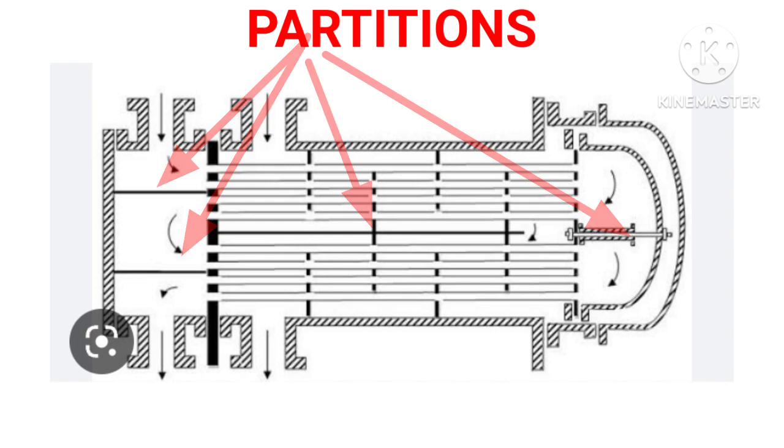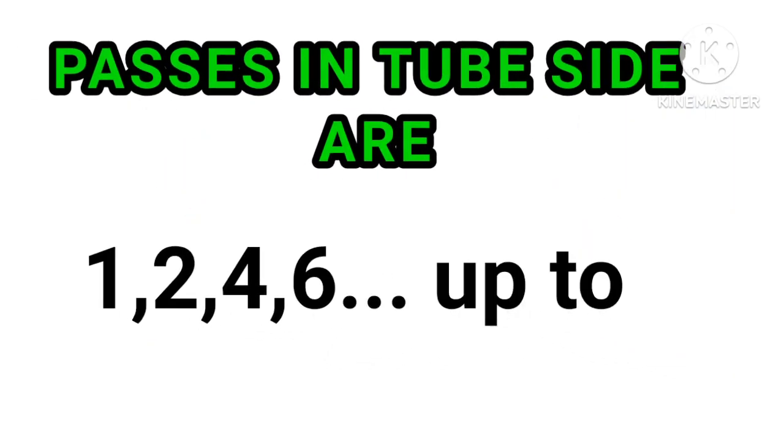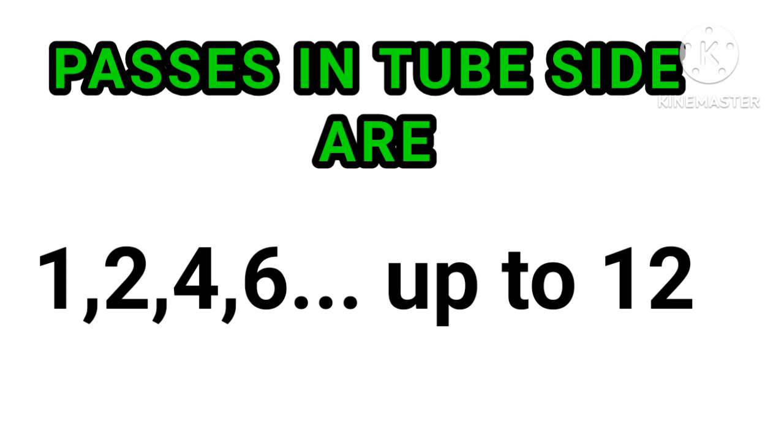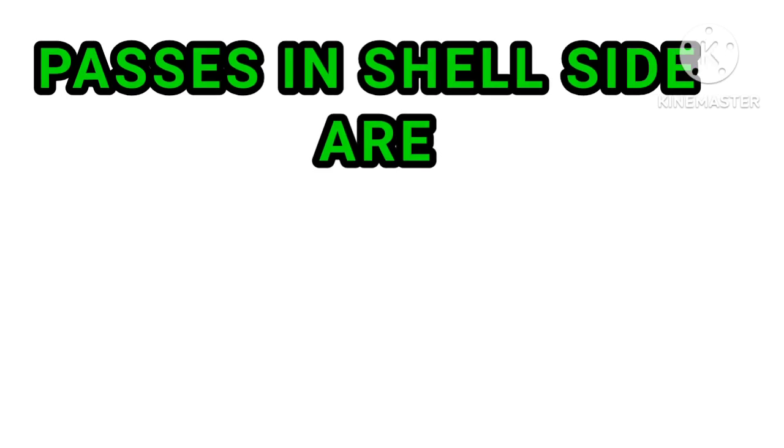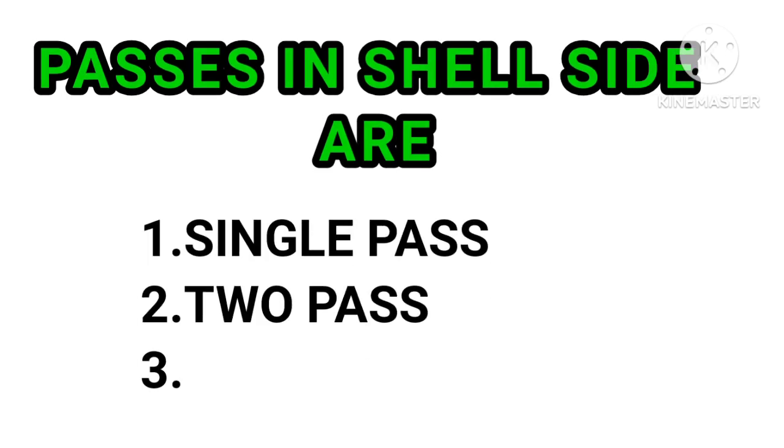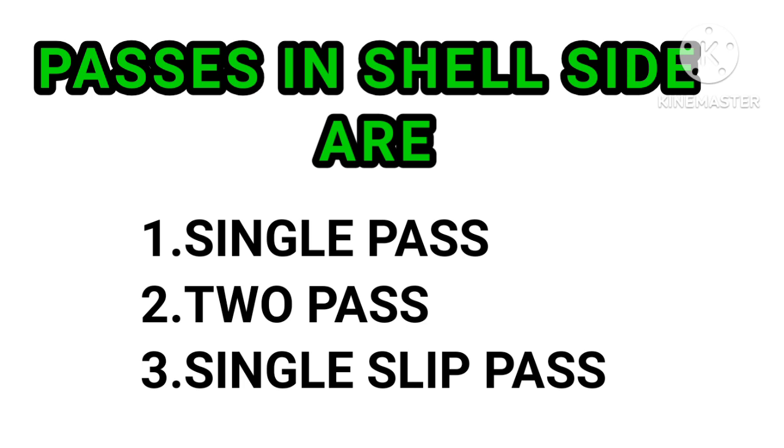Now we will learn about passages. Passes are formed by partition plates in shell cover and channels in tube-side as shown in figure. The passages on the tube-side can be one, two, four, six, up to twelve, and passages on shell-side include single-pass, two-pass, and single-slip-pass.